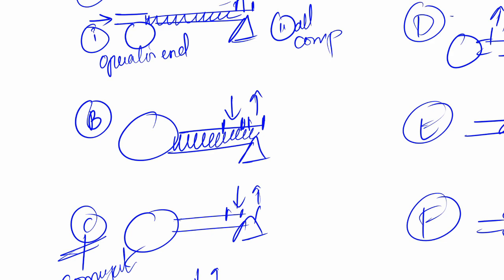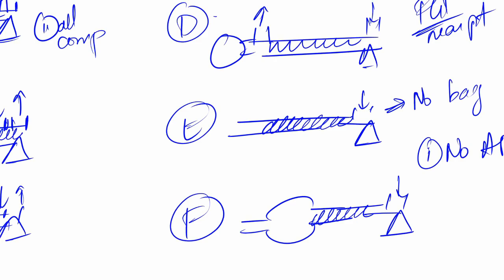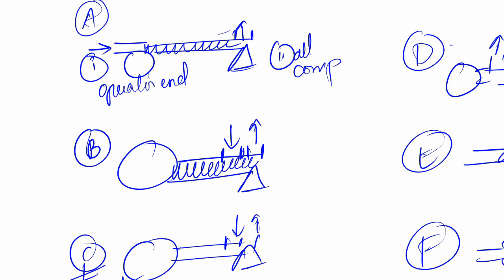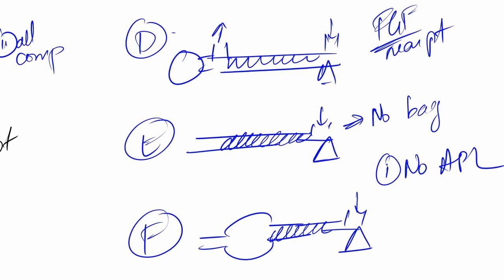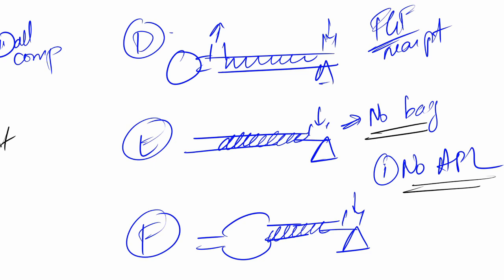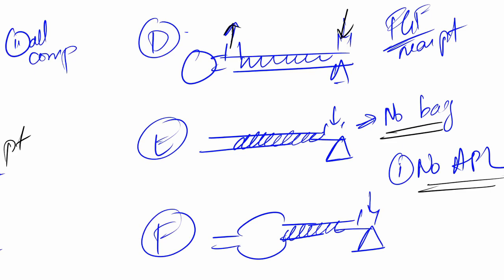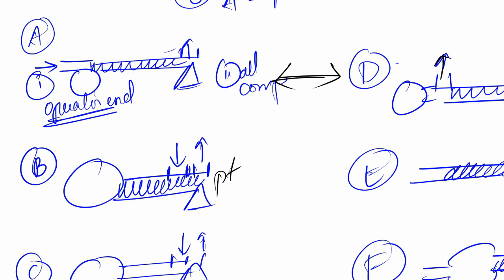To summarize identification: A has all components with fresh gas at the operator end. B has all components but fresh gas is towards the patient end. C is the same as B but without a corrugated tube. E and F do not have an APL, and E does not even have a bag. D has FGF nearer to the patient and APL at the other end — essentially a reversed version of A in terms of FGF and APL positions.